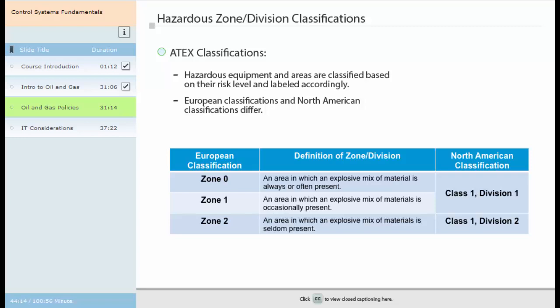In Europe, Zone 0 is an area in which an explosive mix of material is often or always present. Zone 1 is an area in which an explosive mix of materials is occasionally present in normal conditions. Zone 2 is an area in which explosive mixes are seldom present in normal conditions but may accidentally occur.